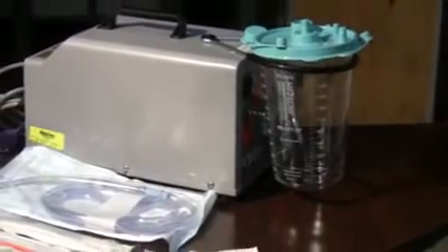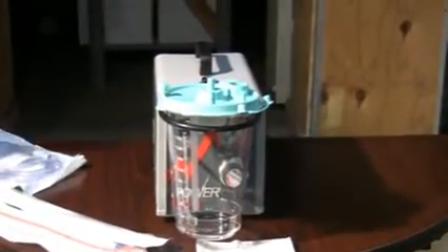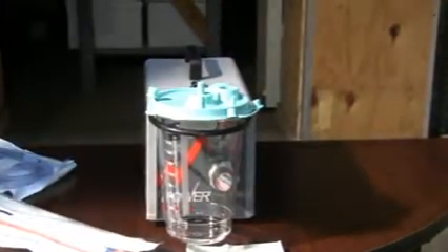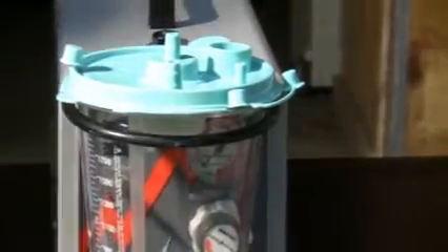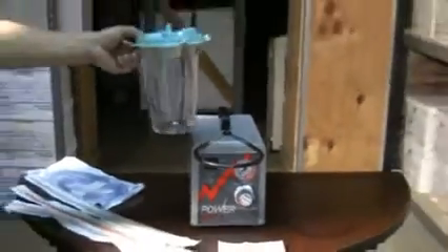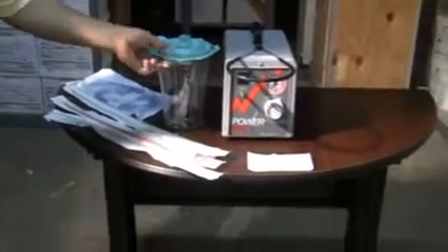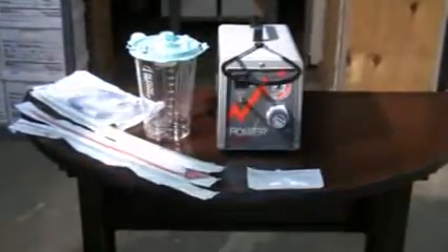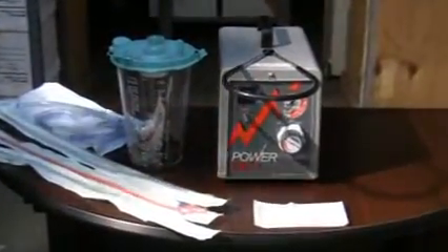As we begin to set up your intermittent suction machine for proper use, we will first go over a few features of the actual intermittent suction machine so as to know how to operate and set it up properly for proper use. When you first receive your intermittent suction machine, your suction canister may be placed in the suction holder directly mounted in front of your intermittent suction machine. What you would like to do at that time is remove your suction canister first, so as to inspect your suction canister for any cracks that may cause a leak or a possibility for there to lose vacuum pressure.